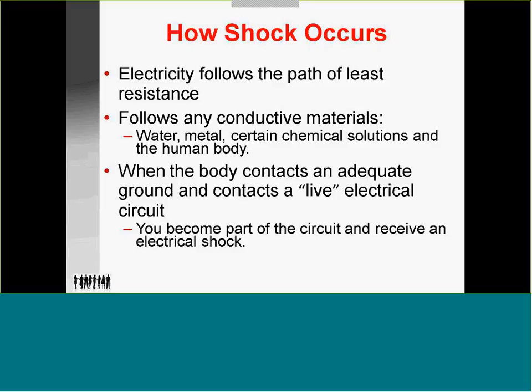By OSHA, in California, a missing ground prong on a power cord, not an insulated tool but a ground-wired tool, or on the extension cord itself, is a minimum $18,000 fine. A plug can also be reversed in the outlet, causing a reverse polarity. If you're using a drill motor that has a metal housing and it requires a ground and you reverse polarity, when you plug it in correctly, the inside is energized and the outside is neutral. When you reverse polarity, the outside is energized and the inside is neutral. So if you're holding that and grab onto a water pipe that's well grounded or any grounded material, current has the potential to pass through.